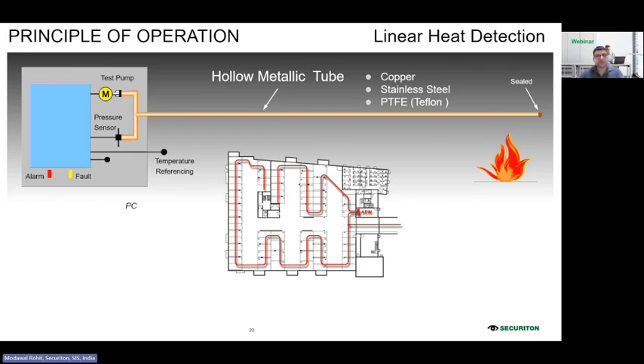The tubes, you can see on the top, are made of copper, stainless steel, or Teflon. Three kinds of tubes you can use. And these tubes are filled with normal air and connected to a detection unit. You can see on the left hand side, we have a detection unit, and these tubes are connected to this detection unit. Inside this, we have a highly sensitive pressure sensor.